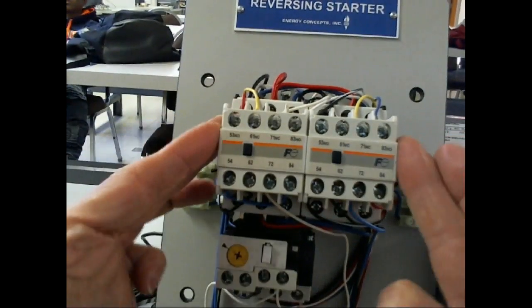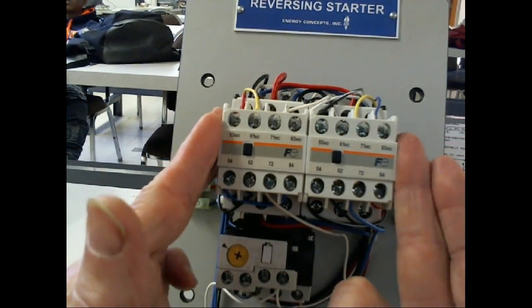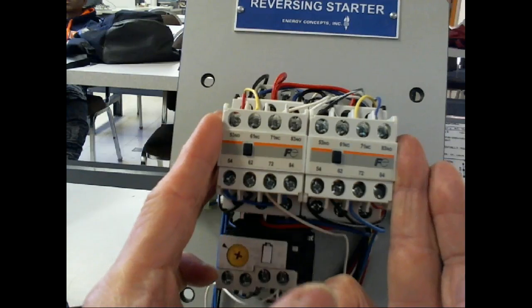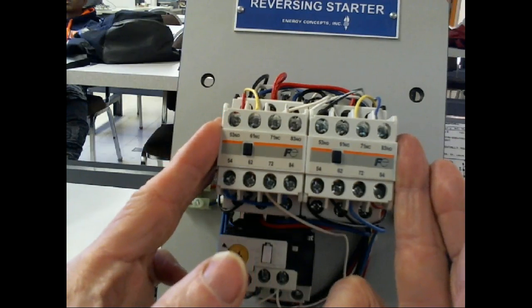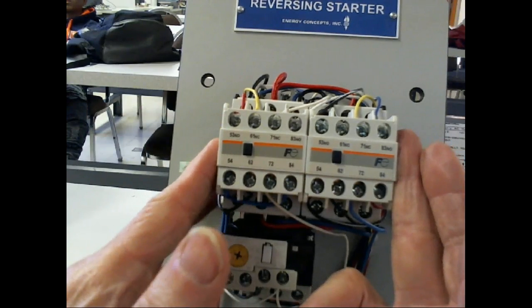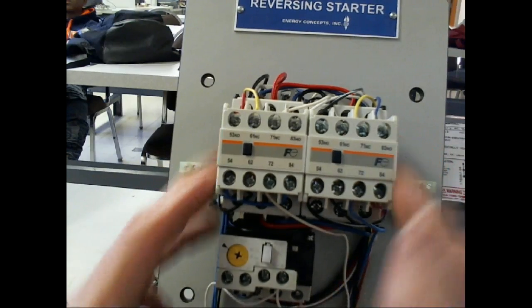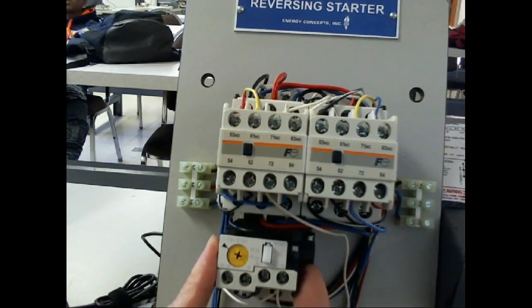So these are the motor. This would be a typical motor starter. It's got both the forward and reverse side by side. Which one's forward and which one's reverse? Doesn't make any difference, guys, it's how you wire it. And then they both feed through this one overload, because they both run the same motor. Understand? Make sense?